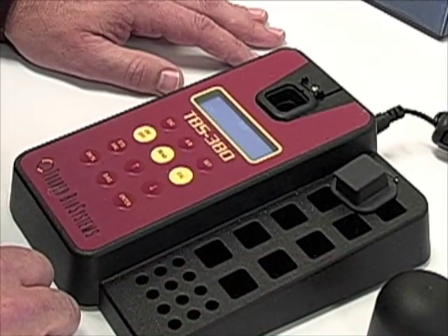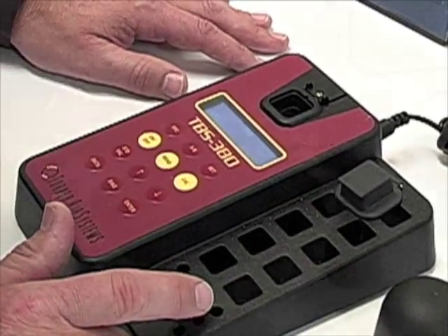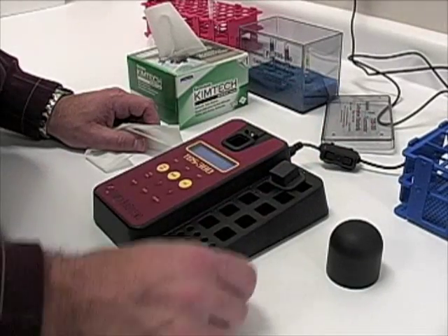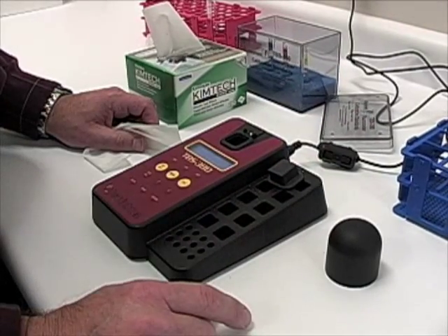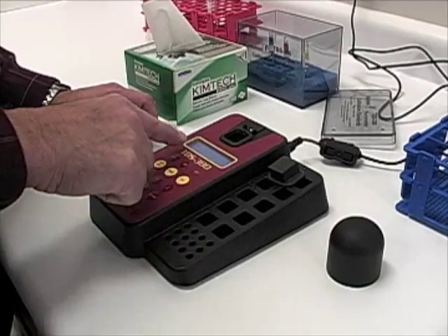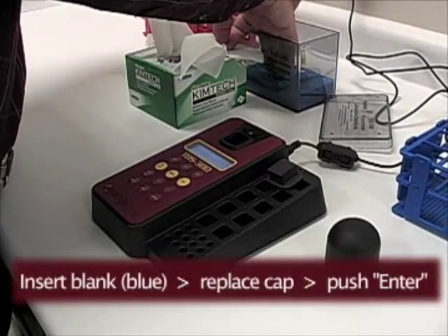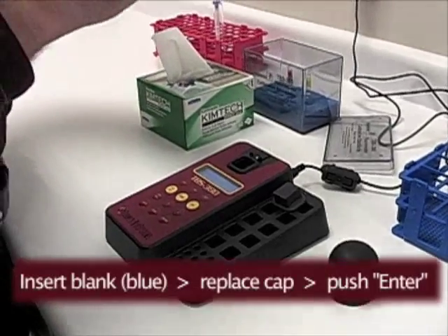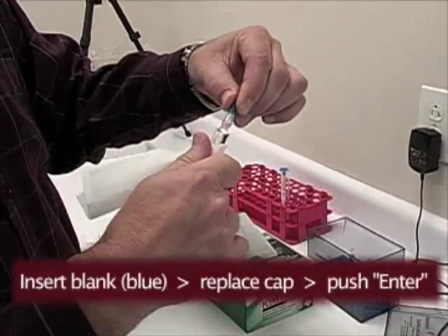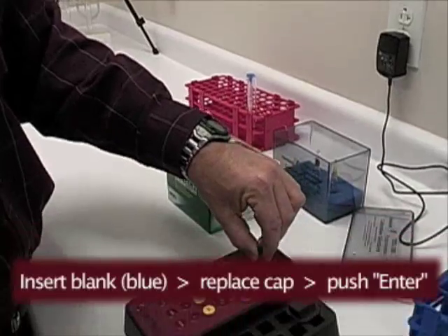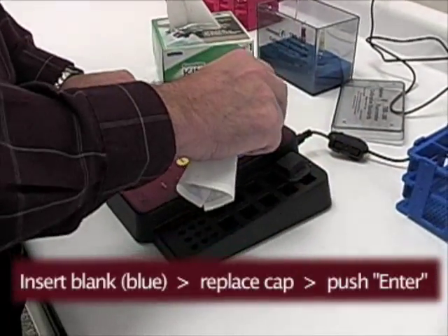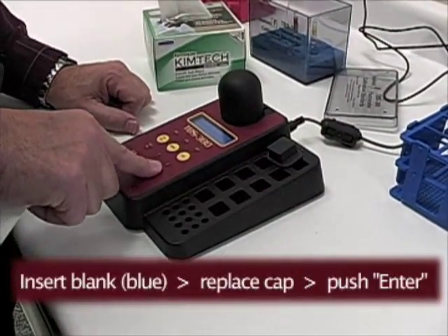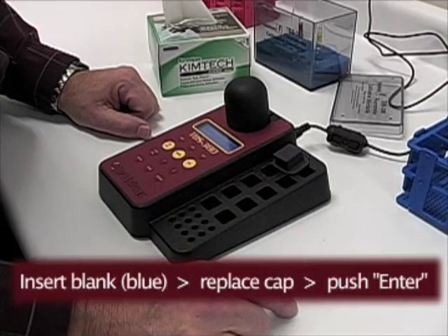The next thing to do is calibrate. In order to properly calibrate the machine, you press calibrate. It says press enter to start. It says insert blank. The blank is this blue sealed ampule. Wipe it clean to make sure there's no fingerprints. Place it in, push the cap over it, and push enter. It is now reading the blank.